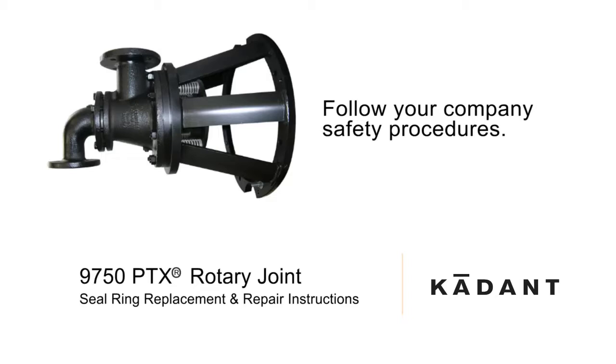Lubricate all fasteners with anti-seize compound. Tighten all fasteners in a star pattern. Torque specifications are listed on the product assembly drawing and are available from Kadant Johnson. Do not use anti-seize or petroleum-based products on O-rings. Only lubricate the O-rings with the silicone lubricant supplied with the Kadant Johnson repair kit.